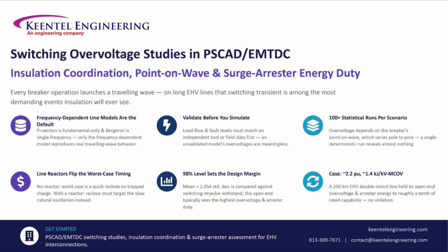Let's close out on why switching transients matter so much. Every time a breaker operates, it launches a traveling wave down the line, and on long extra high voltage circuits, that switching event can be one of the most demanding things the installation ever experiences. Getting the model right starts with the line itself. A simple pi section only captures fundamental frequency, and Bergeron only captures one frequency. Only a frequency-dependent line model actually reproduces real traveling wave behavior, which is why it's the standard for this kind of study.